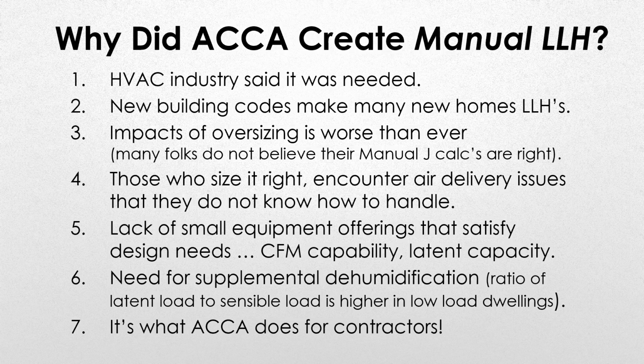Those of us that have been in the apartment market, we've known that for years. But things were more forgiving then than they are now, so you could get away with oversizing, and you can't do that so much. We also find that there's more need for supplemental dehumidification. The ratio of latent load to sensible load is higher in low load homes. So what happens is, say in a 2,000 square foot home, the latent load pretty much stays the same, and it's the sensible that drops.